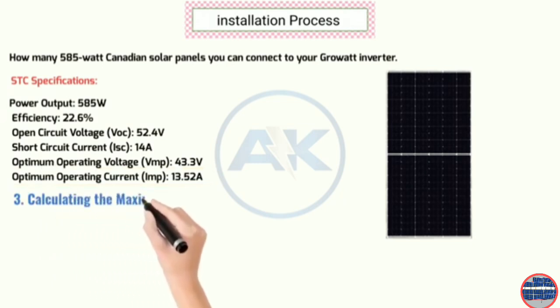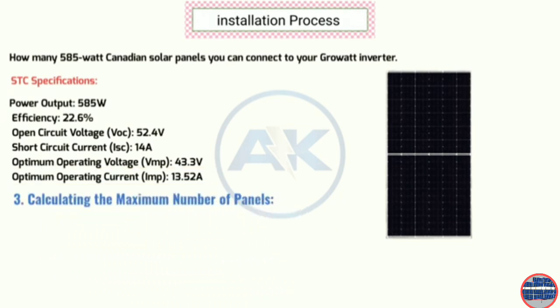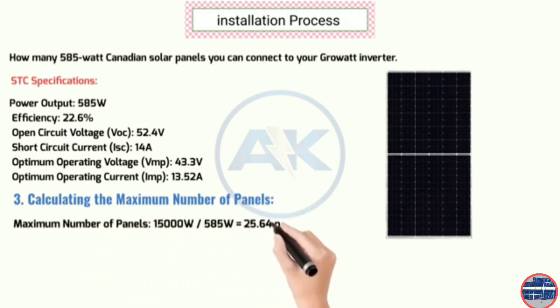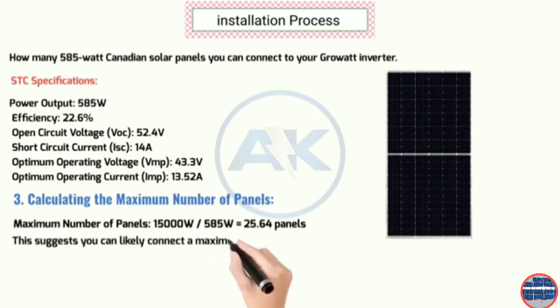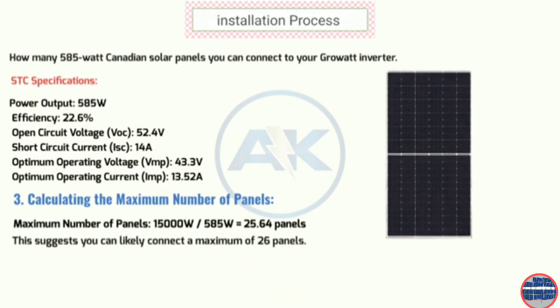3. Calculating the maximum number of panels. Divide the inverter's maximum PV input power by the panel wattage. 15,000 divided by 585 equals 25.64 panels. This suggests you can likely connect a maximum of 26 panels.